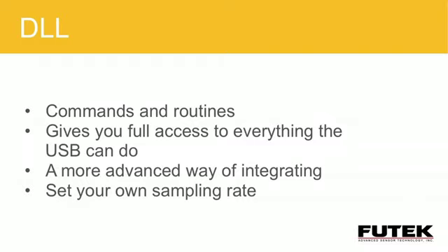Now let's take a look at the FUTEK USB DLL. The use of the USB DLL will require some software development experience. The commands used by this DLL have a send and receive type of communication. You have full access to the command set, including the ability to request information from the device, to completely configure the device, and even to calibrate the device. The USB DLL can be used for more advanced integration into your system as well.